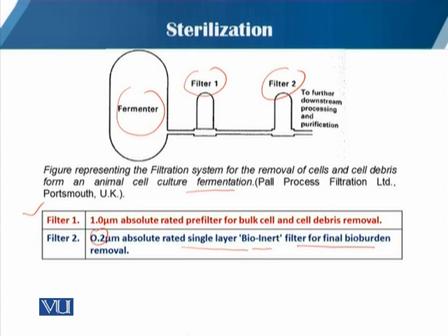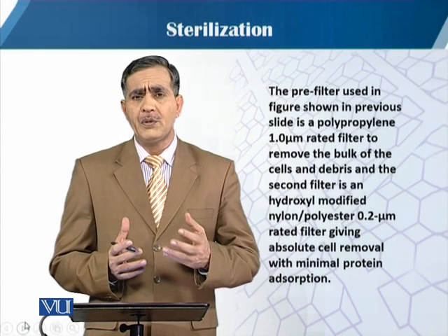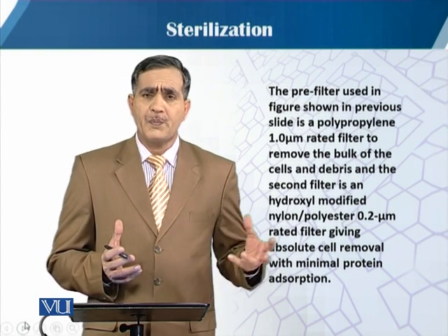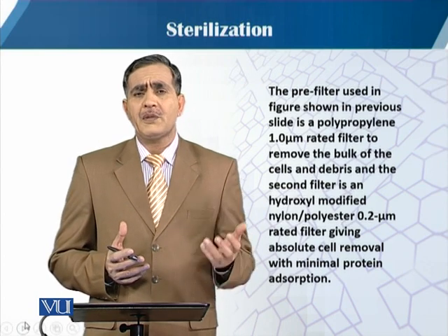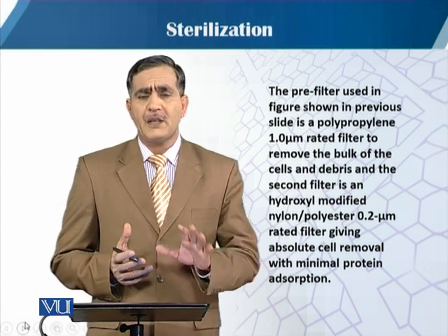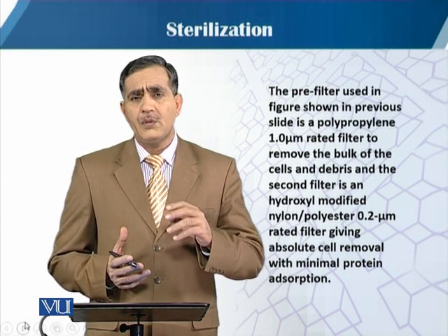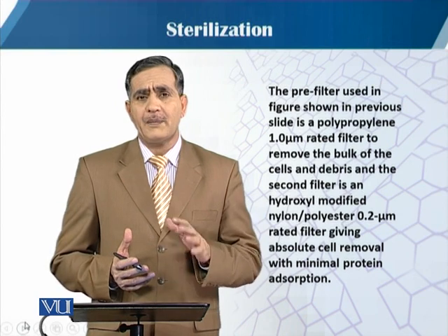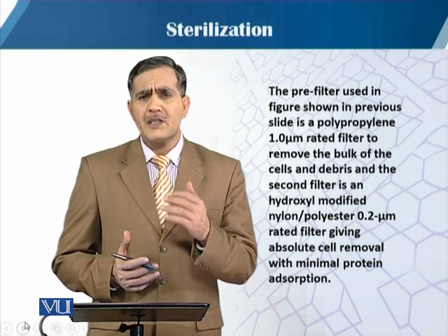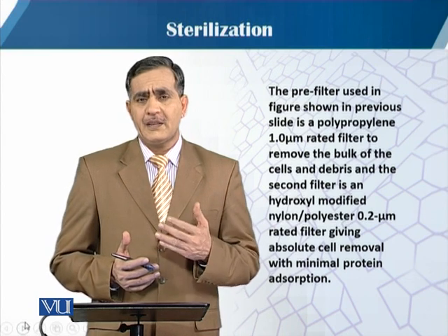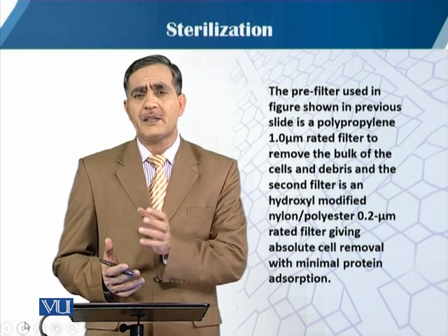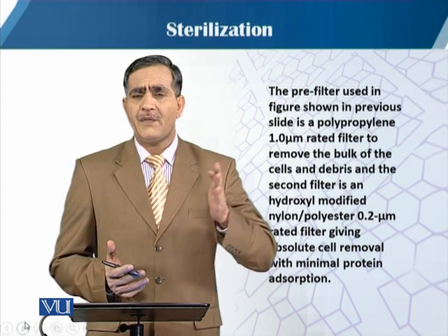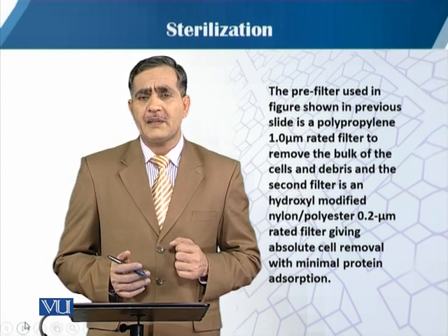Pre-filters are mostly used for the removal of coarse particles — especially the bigger particles. If we are not using pre-filters, there is a chance of blockage of the fine filters. To avoid blockage and thus to increase the life of the filters, pre-filters are needed. We line up all the filters with decreasing pore size from the first to the last in the series. Using filters in series gives us the assurance of proper sterilization.